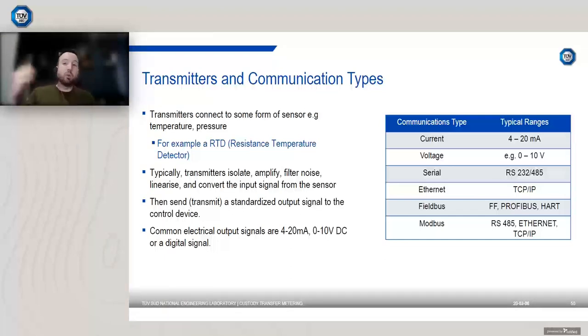So they've all got their advantages and disadvantages. Digital communication protocols tend to be able to give you more diagnostic information. Digital instruments, typically the upfront cost is more expensive. And 4 to 20 milliamp is still widely used. It's not going anywhere. So again, I'm not going into too much detail here, but there's advantages and disadvantages to each type of comms protocol.